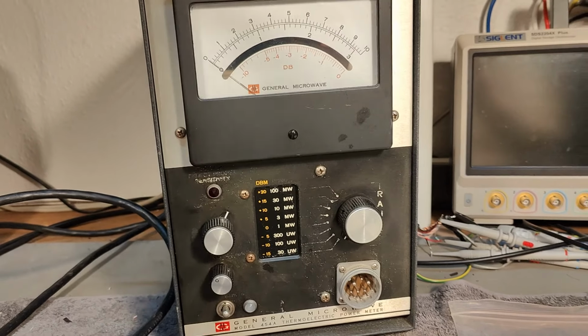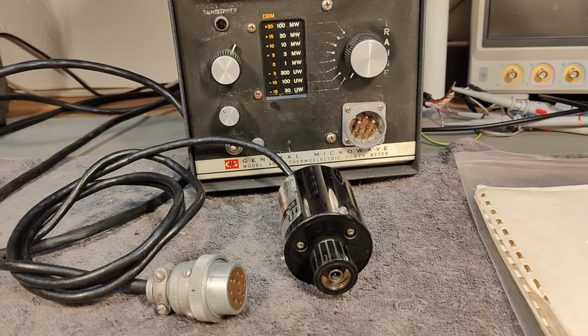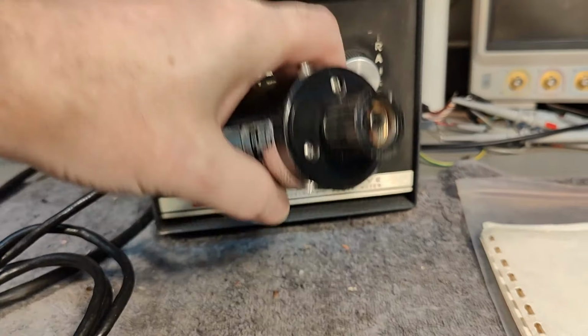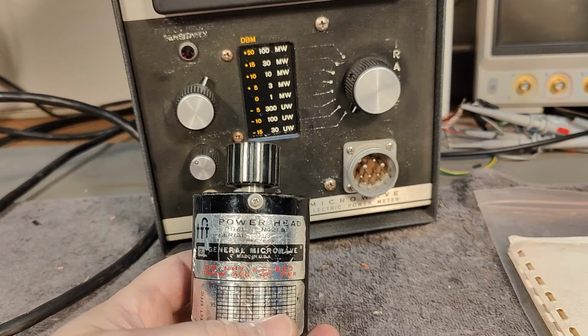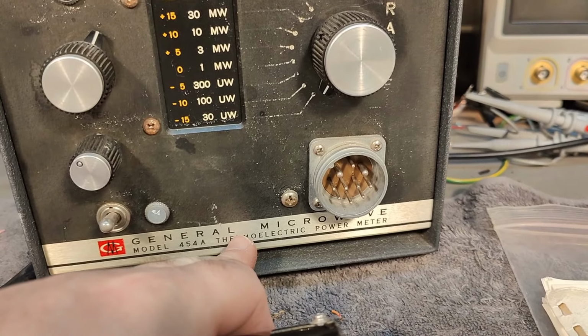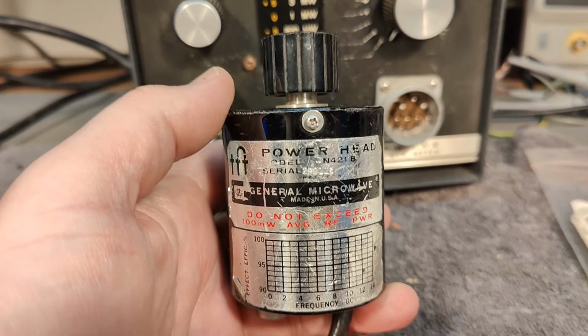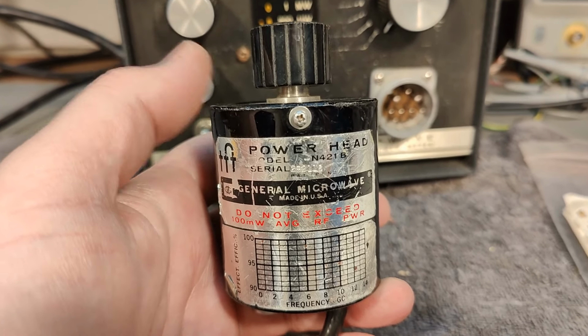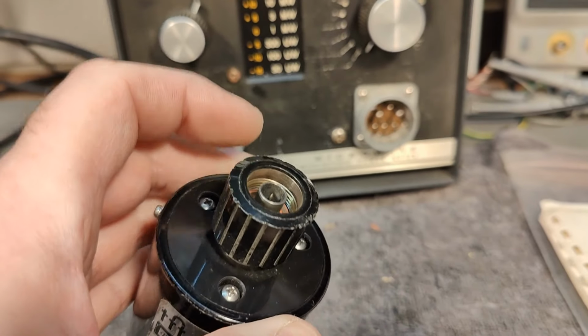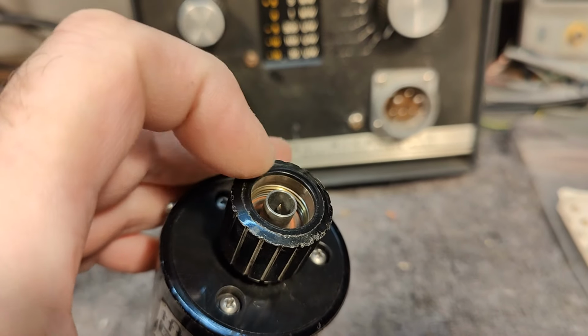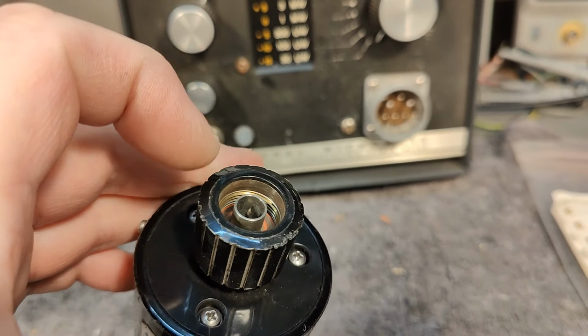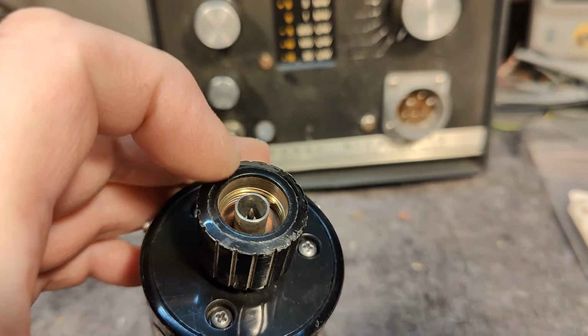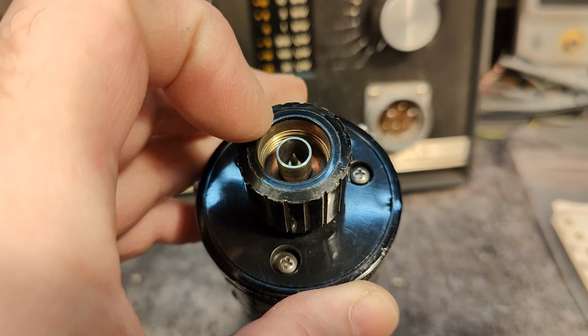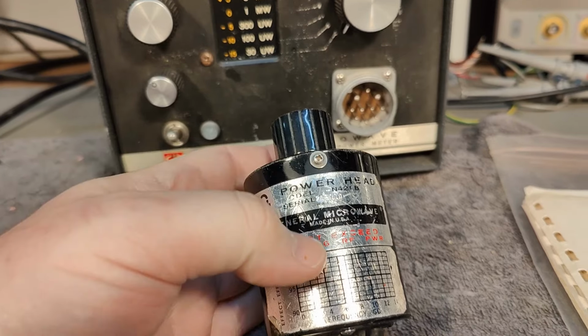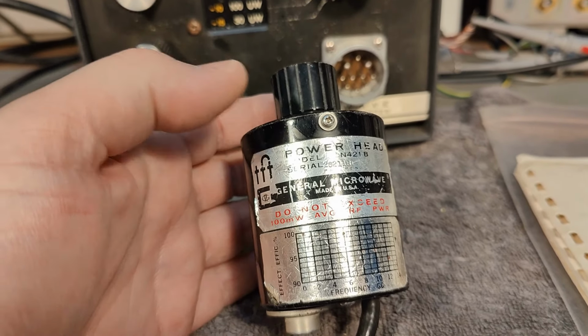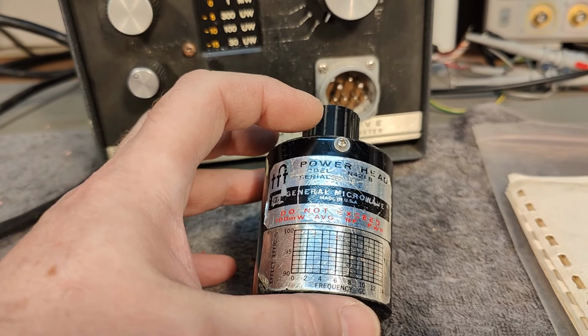I also got the probe. And this probe here, you've probably already figured this out since it says thermoelectric. That means inside this probe we got 2 temperature sensors. One temperature sensor is directly connected to the input, of course via a little bit of matching and all that kind of stuff. But that temperature sensor is heated up by the RF input power. All right, and then there's another reference temperature sensor of exactly the same type, and it's measuring the ambient temperature.